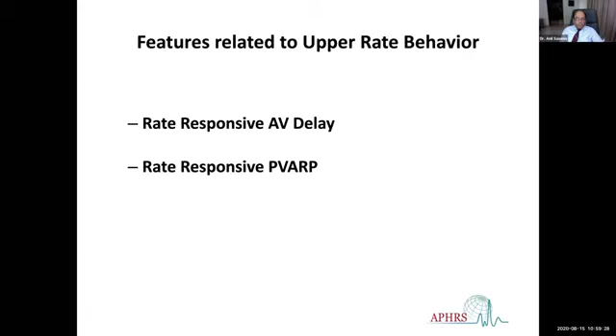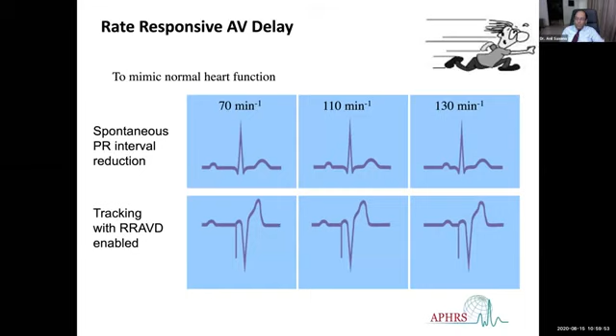Now, it may not be possible to reduce the AV delay all the time. And if we reduce the PVARP too much, then there may be other problems. So now, in almost all pacemakers, we have a function called rate responsive AV delay, where the AV delay becomes shorter as the heart rate increases, and that actually mimics normal heart function. We all know that as we increase our heart rate, the AV delay gradually shortens, the PR interval shortens. The same thing can be programmed to be mimicked by the pacemaker, that with increasing heart rate, the pacemaker will shorten the AV delay, and that will allow a higher tracking rate.